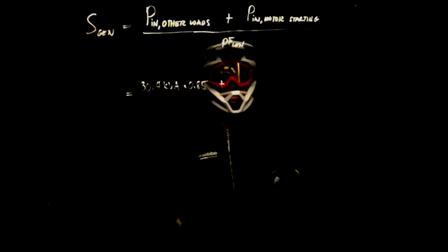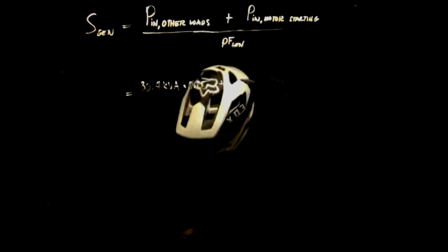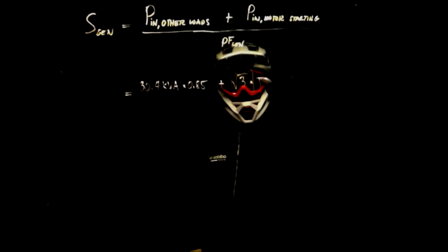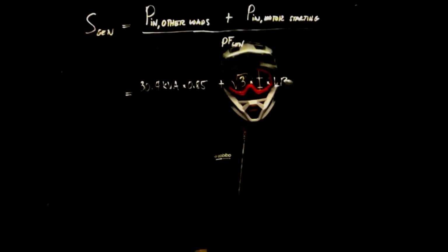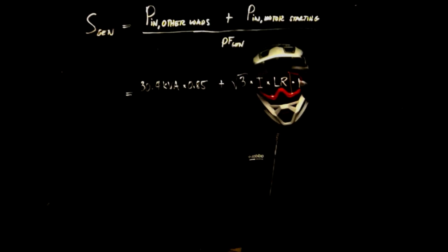Then for your lock rotor, that will be square root of 3 times your I times your lock rotor multiplying factor times your rated voltage times the starting power factor.